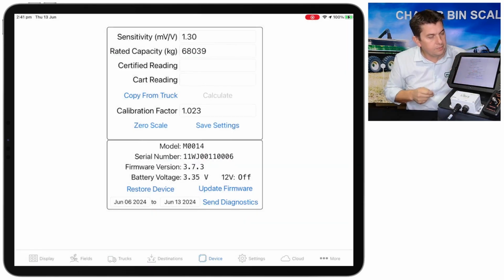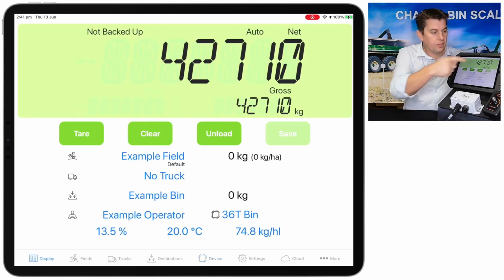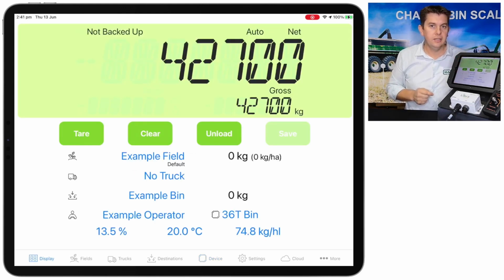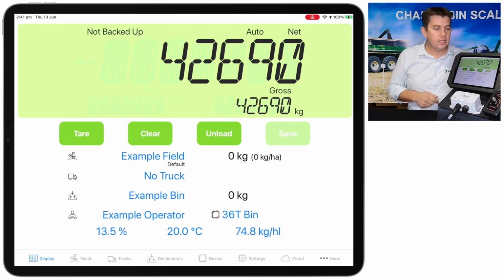It's just giving us a warning. We're going to change that calibration again, and you'll see the numbers have then gone black to let us know it's saved it. If we go back to the display tab, the numbers will have changed again. Just like before, we can do that with weight in the bin or not, it doesn't matter. It's just adjusting that calibration factor to that known weight. So that's about it for this one.